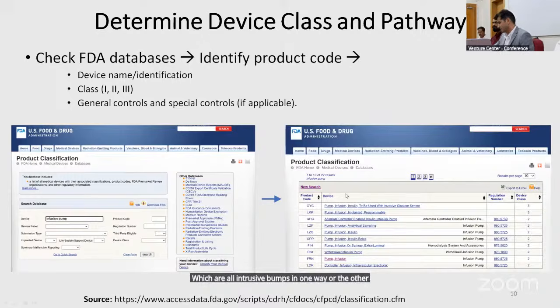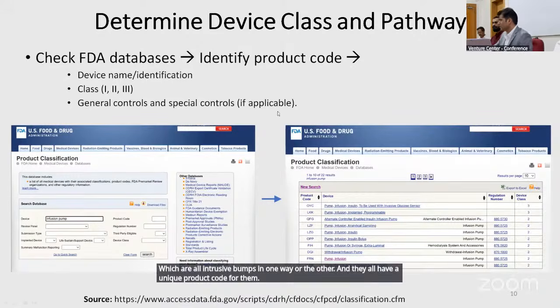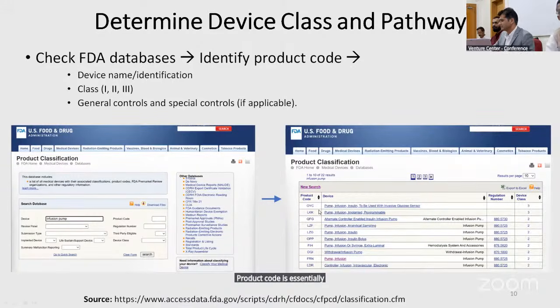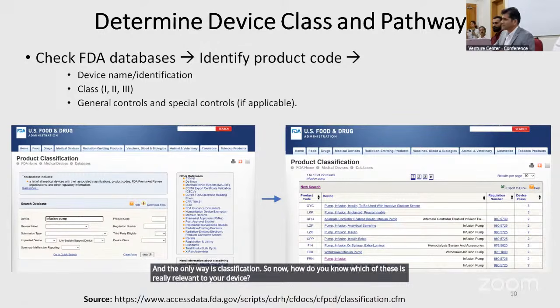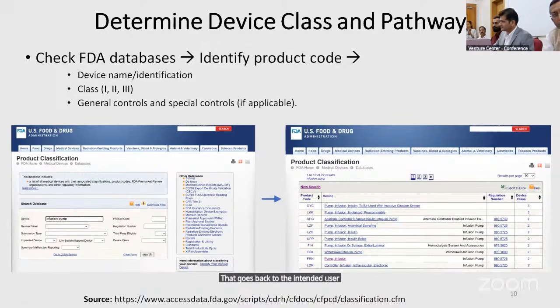And they all have a unique product code. The product code is essentially the 3-letter code you see on the left there. Then it also gives you the regulation number on the right and the device classification. So now, how do you know which of these is really relevant to your device? That goes back to the intended use and indications for use. Based on all these lists, whatever is closest to your device and its intended use is most likely going to be its product code.